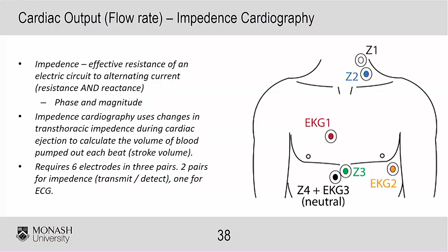It essentially uses the changes in transthoracic impedance during cardiac ejection to calculate the volume of blood pumped out each beat, which is the stroke volume. If you know the stroke volume and the heart rate, you can calculate the cardiac output because you just multiply the two. It requires 6 electrodes in 3 pairs. One pair is for the ECG, or in this case EKG, it's exactly the same thing, and 2 to detect changes in impedance. High frequency, low magnitude current produces a baseline impedance across the electrodes, and then you get a changing impedance which correlates to the stroke volume of blood coming out of the heart.